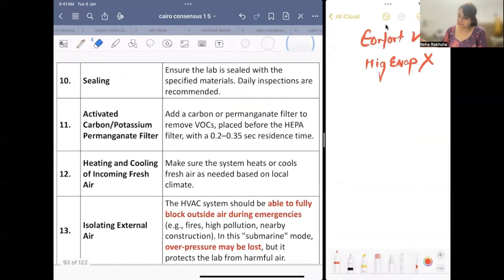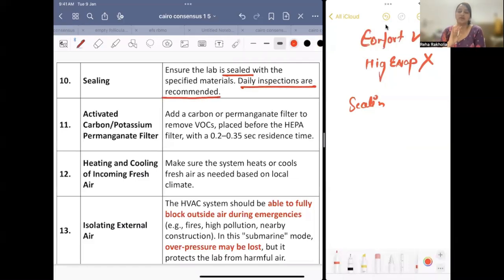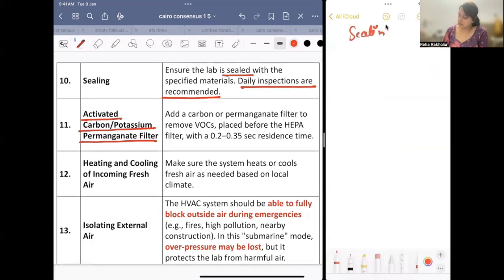Now sealing. Ensure the lab is sealed with specific material. Daily inspection is recommended. The whole lab should be sealed because we have to maintain a positive pressure. We don't want any dust to come in. Now, activated carbon and potassium permanganate filter, and we have to regularly check whether it's sealed or not.